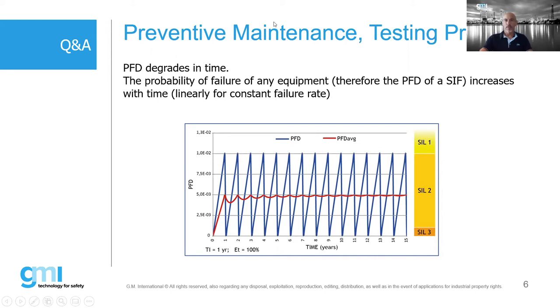So maybe Massimo, we can work. Okay. Let's see, does the power supply also have to be SIL too, or does the use of a galvanic isolator barrier provide its own SIL rated power supply into the transmitter loop?